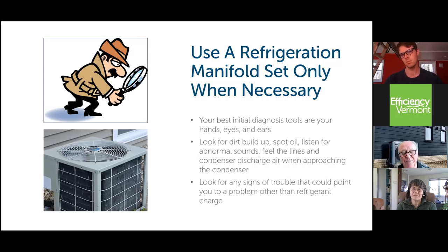You can take a temperature reading on that liquid line. When you have a system that's operating, because we're trying to reject heat into the ambient air, your liquid line is going to have to be warmer than the ambient air. If it isn't, then you have some kind of a restriction. So if your liquid line is warmer than the ambient air, that's a good indication that we're in refrigeration mode. So look at all the other things that could be causing trouble.